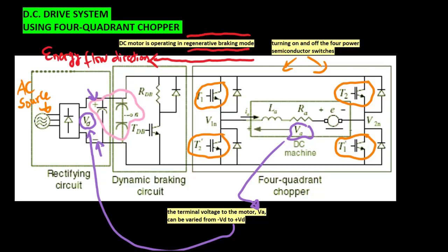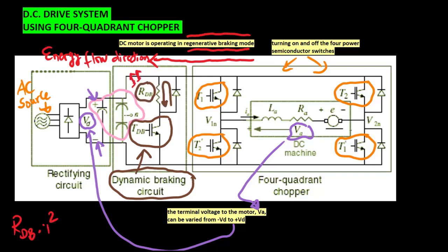To prevent overvoltage of the DC link, a discharging switch implemented by a power semiconductor turns on and the regenerated energy is dissipated at a resistor Rdb as heat. This kind of braking energy absorbing method is called dynamic braking. Through the four-quadrant chopper circuit, the current regulation bandwidth can be easily extended up to several thousand radians per second.